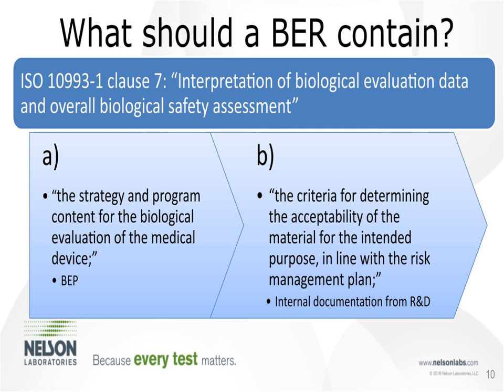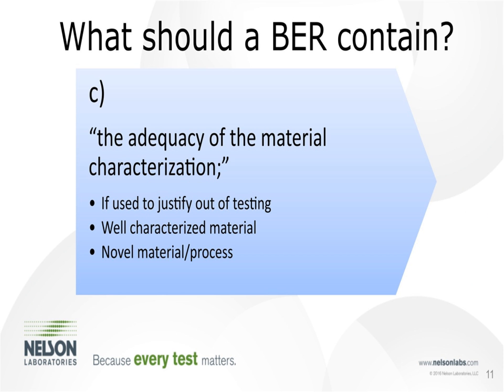Part A covers the strategy and program content for the biological evaluation of the medical device — laying out what the evaluation plan was. Part B covers the criteria for determining the acceptability of the material for the intended purpose in line with the risk management plan, which is typically done well before presenting a final device for testing and should reference internal R&D documentation or a device history file.